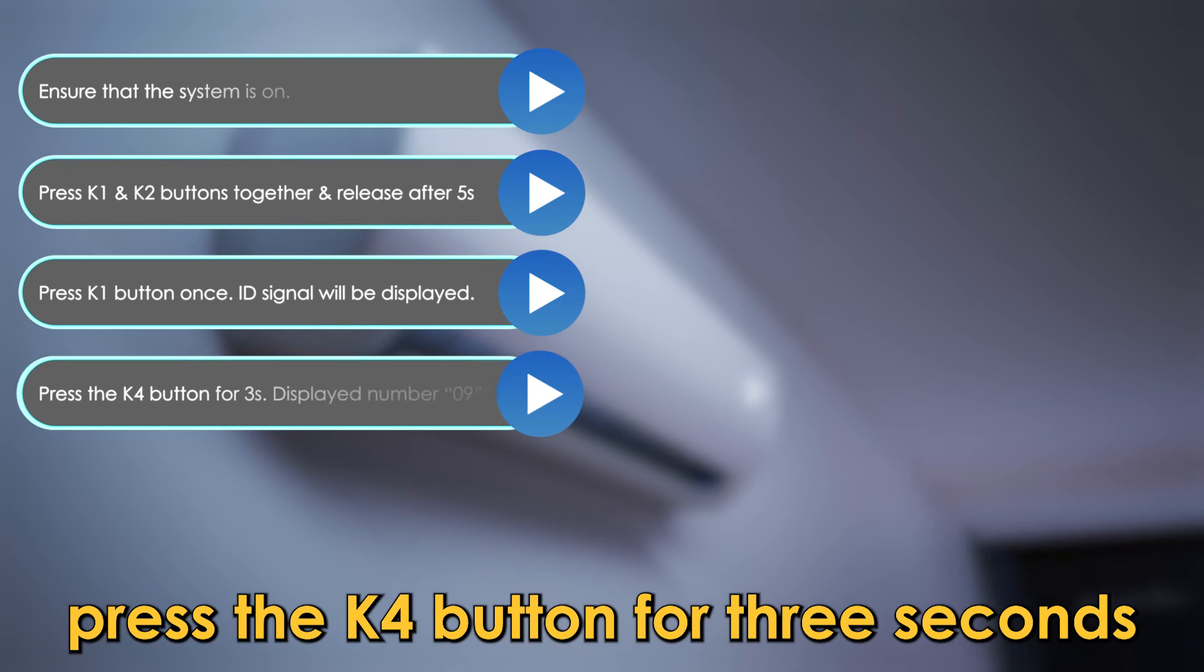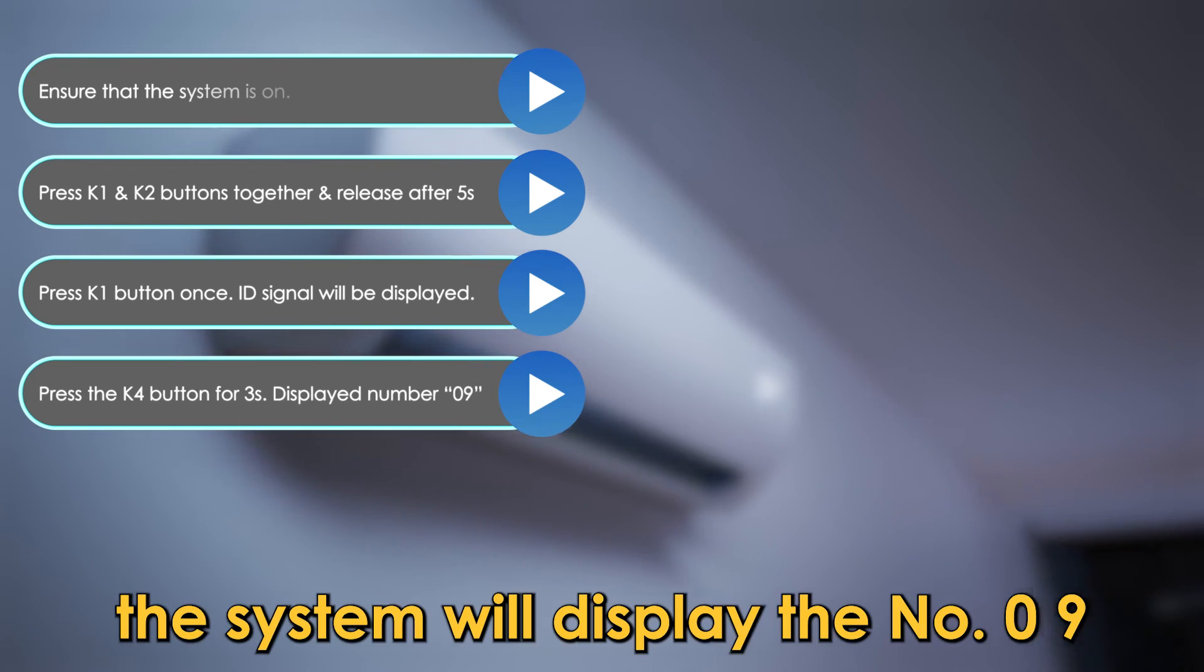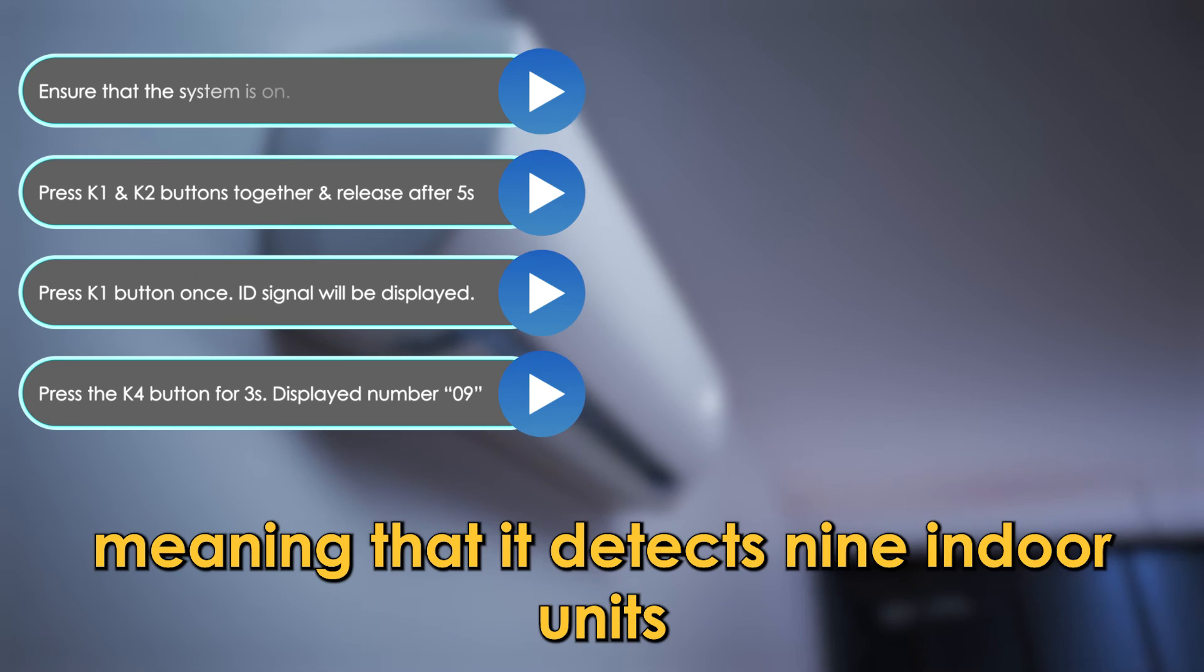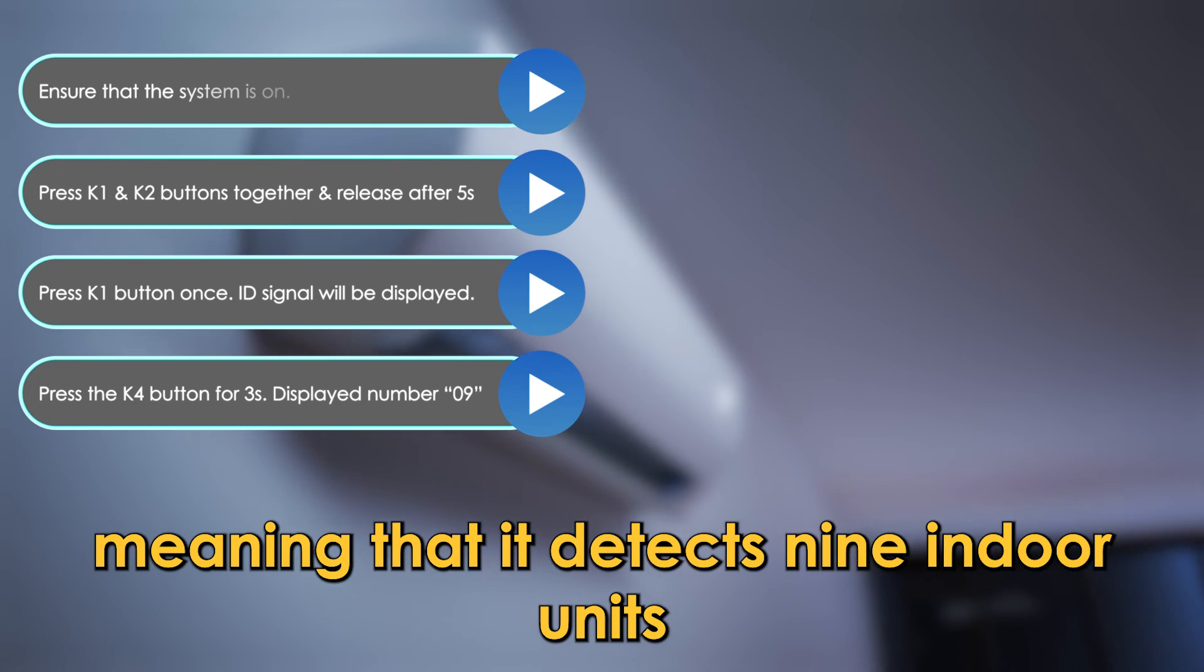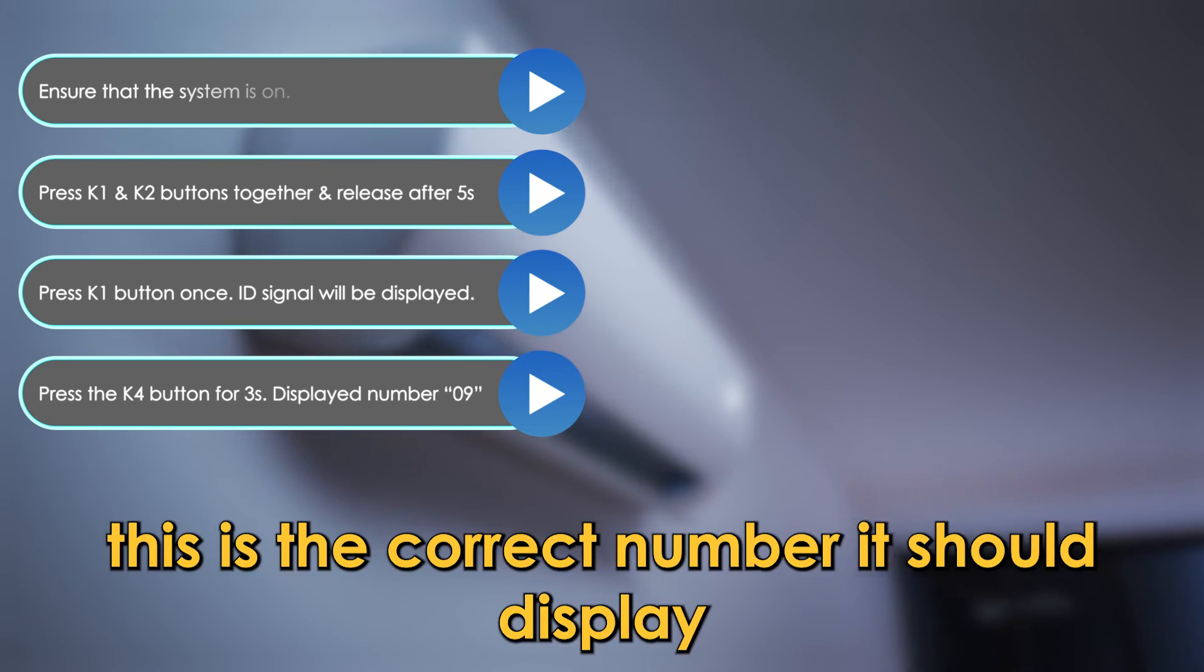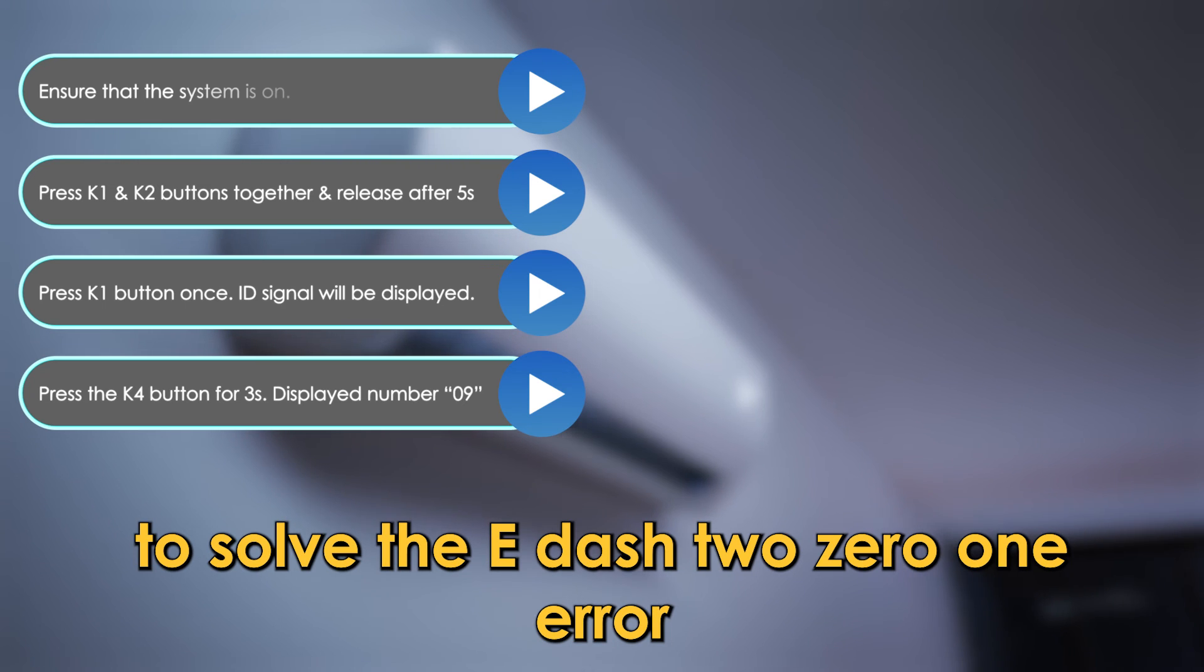Press the K4 button for 3 seconds. The system will display the number 09, meaning that it detects 9 indoor units. This is the correct number it should display to solve the E-201 error.